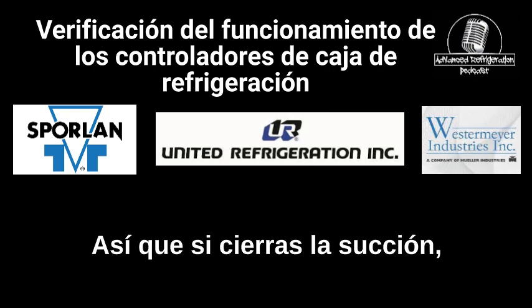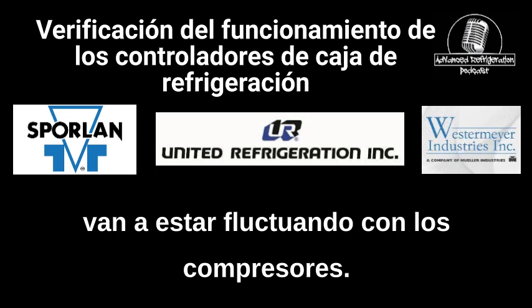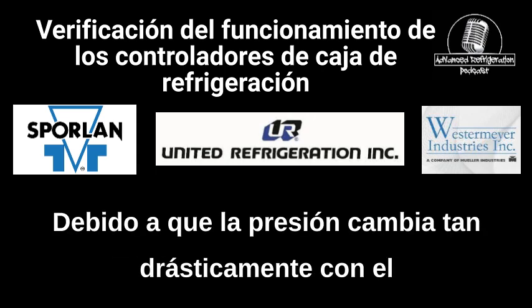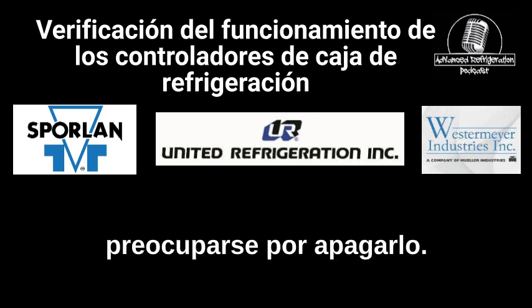So if you shut the suction, you're going to be steady 100%. If you shut the liquid, you're still going to be fluctuating with the compressors. Well, how about with the CO2 though? Because the pressure changes so drastically with the temperature. Yeah, everything checks back to the liquid. True. So you don't have to worry about that. It all checks back. So don't worry about shutting it off.